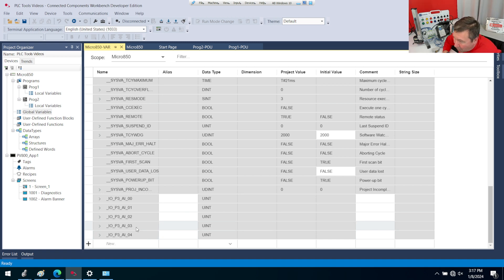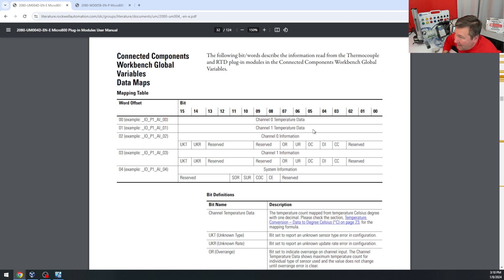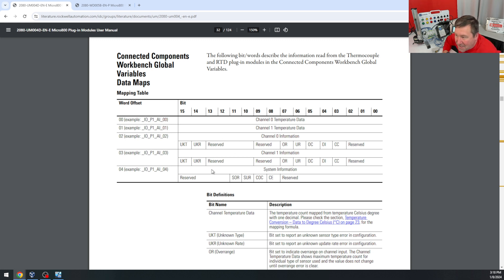But this is only a two-channel module. If we look in the user manual, there's our 0, 1, 2, 3, and 4. Analog 0 is channel 0 temperature data, which we've used in the previous two videos, and 1 is channel 1 temperature data. But then 2 is channel 0 information, and 3 is channel 1 information.